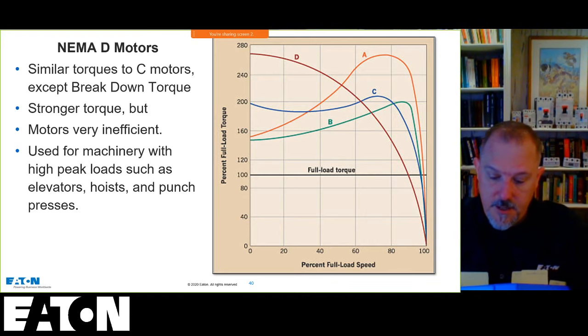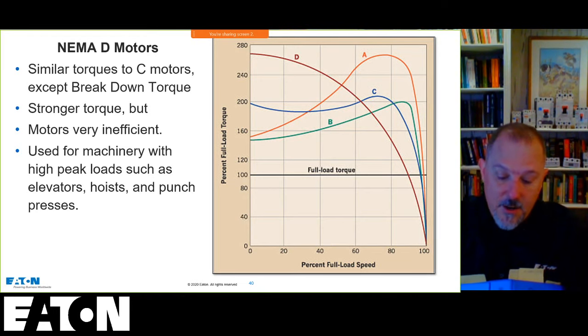And it tells you table values other than for motors built for low speeds or high torques, and for multi-speed motors, the values given in 430.247, 248, 249, and 250 shall be used to determine the ampacity of conductors, blah, blah, blah, instead of the actual current rating on the motor nameplate. Where a motor is marked in amperes but not horsepower, the horsepower rating shall be assumed to be that corresponding to the value given in those tables. Motors built for low speeds, less than 1200 RPM, or higher torques may have higher full load currents, and multi-speed motors will have full load current varying with speed.